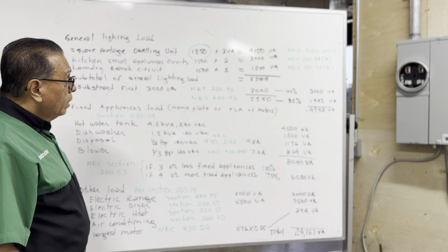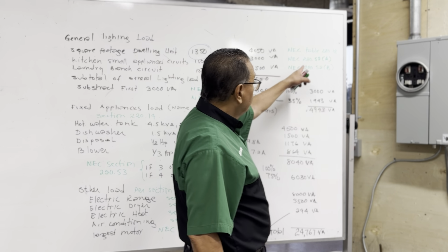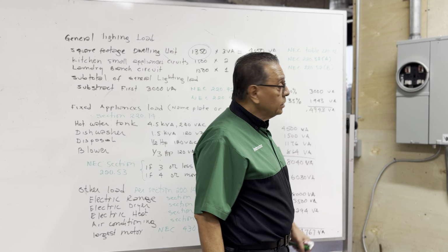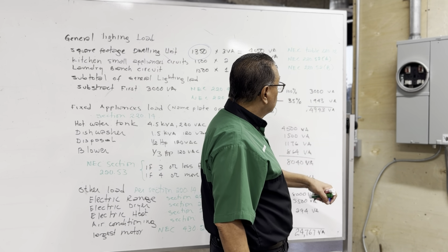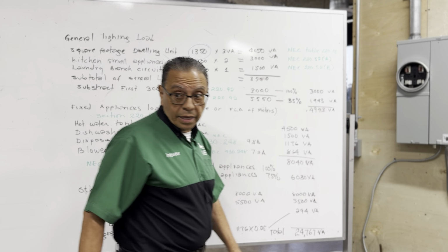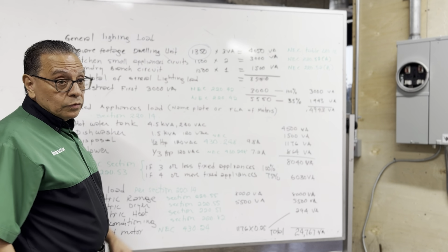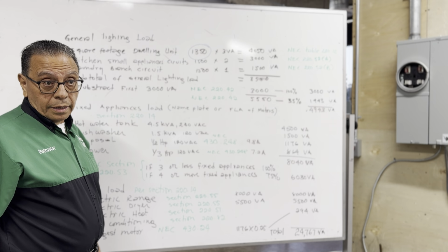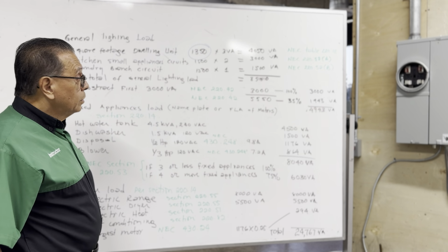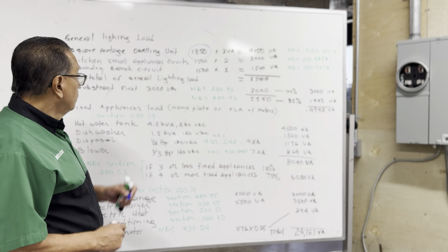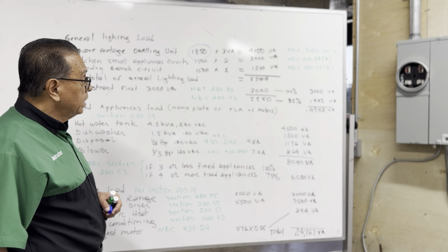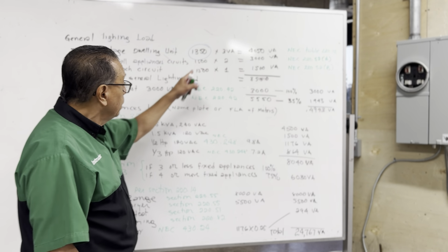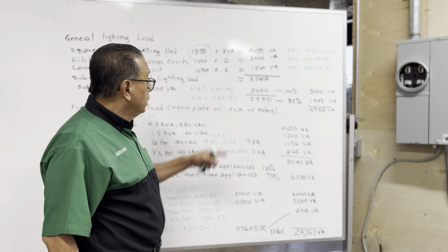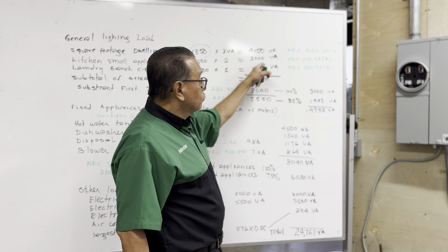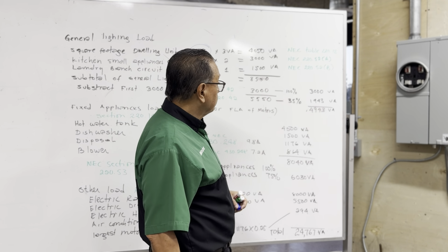Also, the NEC in Article 220.52(A) is asking me to have available 2 branch circuits for small appliances in the kitchen. Each branch circuit should be 1,500 volt ampere times 2. I am getting a total of 3,000 volt ampere.